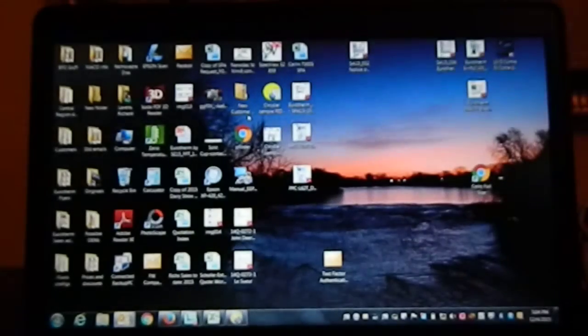And when you click OK, one of two things is going to happen. First, if you click OK and everything's set up right, this window is going to disappear. If the IP addresses don't match between the Nanodac and the PC, you will get a prompt saying that you've got issues. So in my case, we're going to click OK. The window goes away. Down here it shows the IP address. Again, we're going to click OK here. On this window here, you can either minimize it or go to the View tab and hide the server, which is the way I do it.